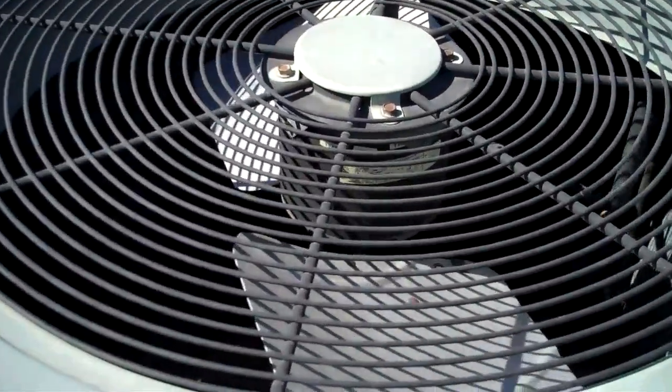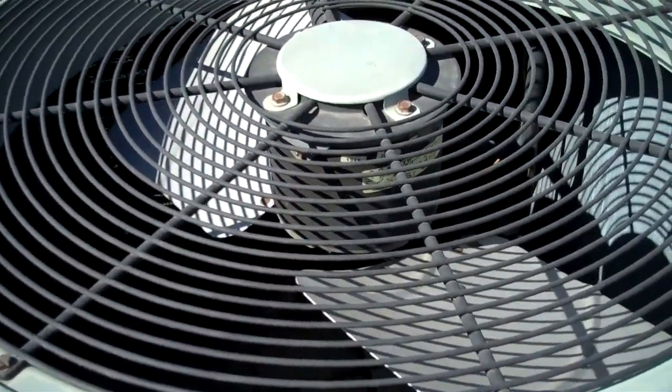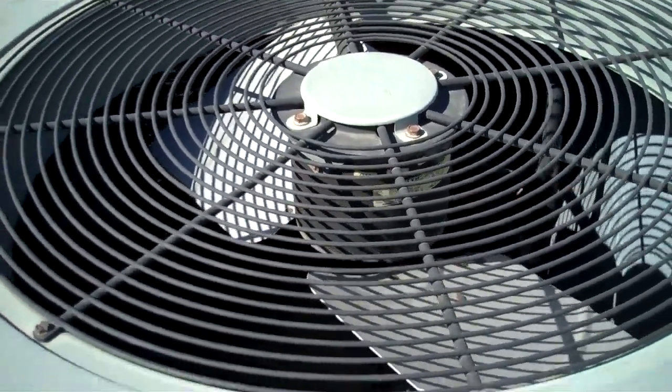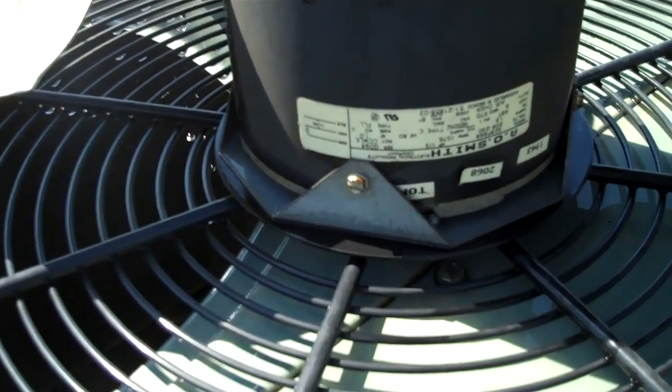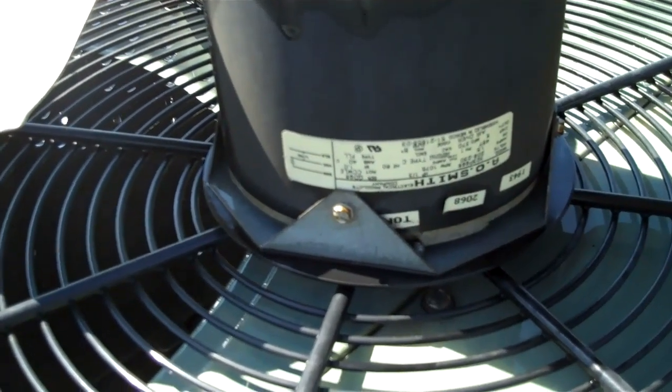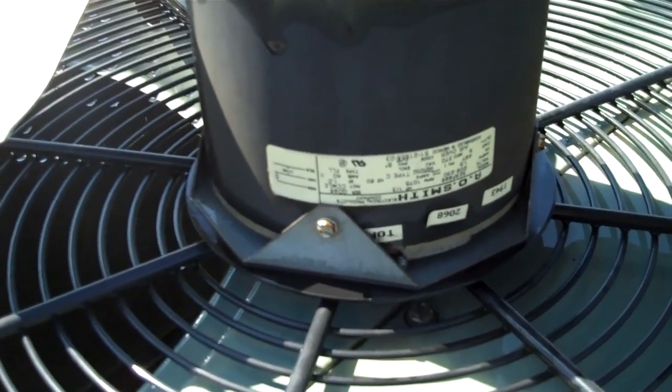We're down and out right now. Bad A.O. Smith fan motor. Bad fan motor. This motor's out — 1/3 horsepower, 1075 RPM, 230 volt.